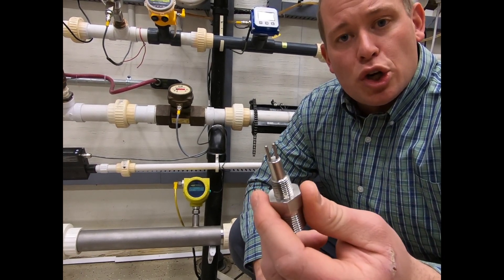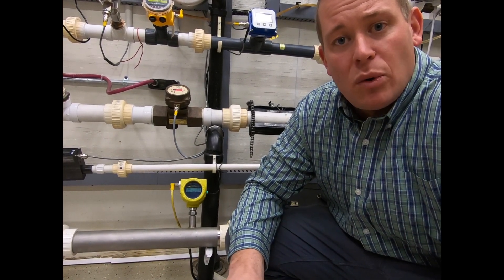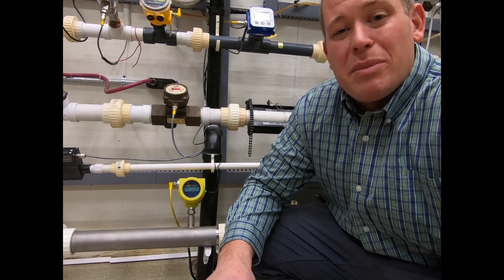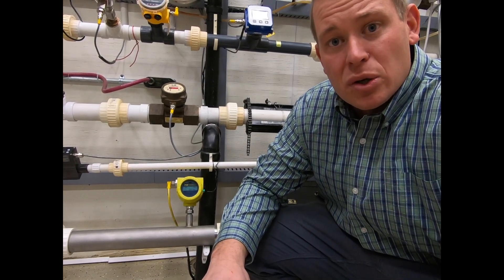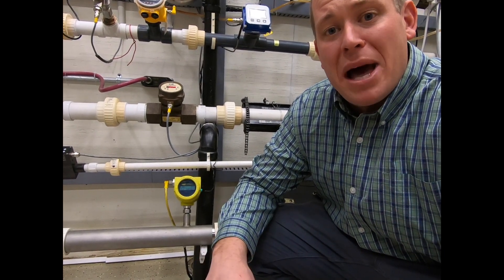So it's got a very large turndown ratio of about 100 to 1 or better, and also it measures directly mass flow rate, so there is no pressure temperature compensation. The meter does that all internally, so that it's actually outputting mass flow rate.